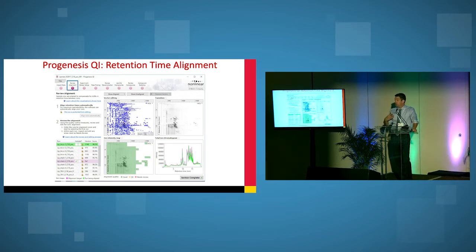For the most part, we don't really deviate too much in terms of what the default settings are in terms of retention time alignment. We do C18 separations. We get very good retention time alignment. Those tend to be very reproducible and we're above 90%, mid nineties or so in terms of that scoring. If by chance that scoring is low, we can go back in and actually modify some of that alignment or what it is. It's a QC parameter that allows us, tells the quality of the chromatography.